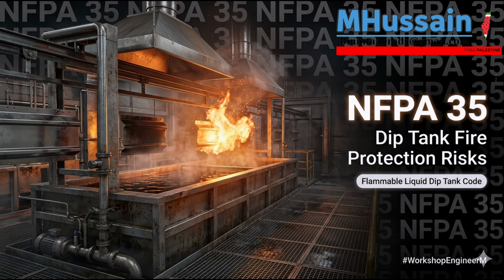The physical phenomenon is called triboelectric charging. When you pump a liquid solvent through a steel pipe, the friction of the fluid molecules rubbing against the interior wall of the pipe actively strips electrons away from the liquid. Yes. The liquid literally generates and accumulates a massive electrostatic charge simply by flowing. Pouring a solvent into a tank, mixing it with a high-speed agitator, filtering it, all of these normal actions build up static charge. And if that high-voltage static charge accumulates on a metal tank or a pipe, it desperately wants to find a path to the earth. It wants to ground itself.